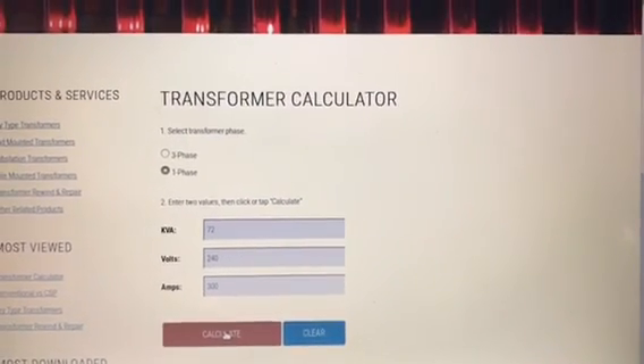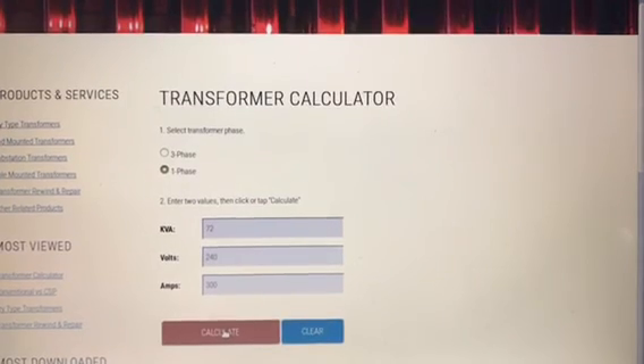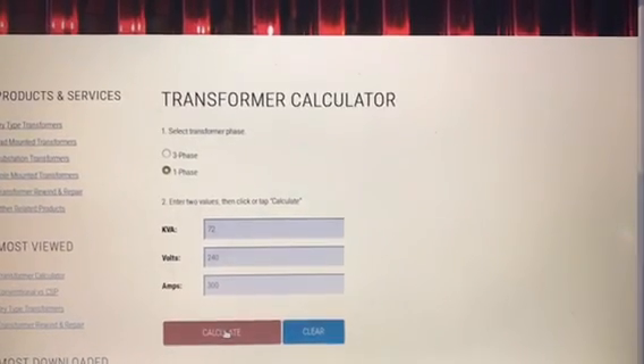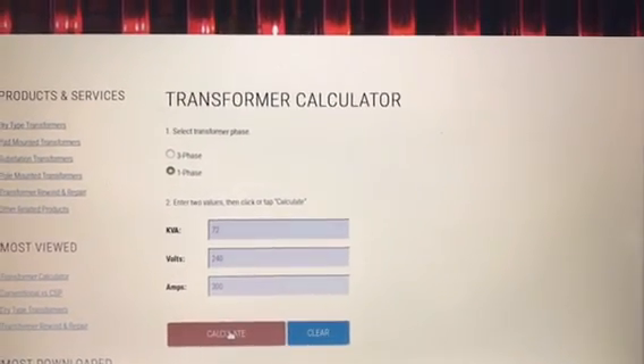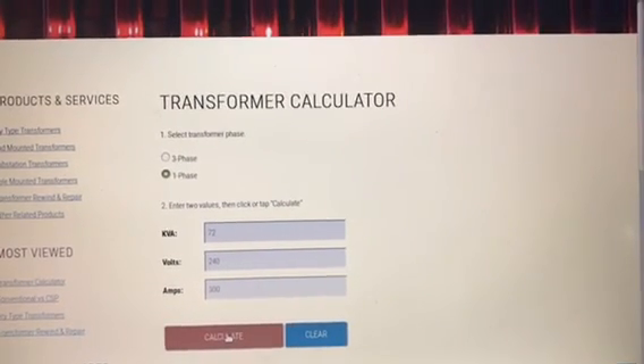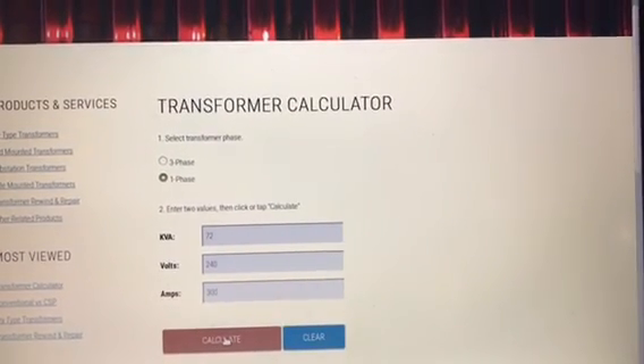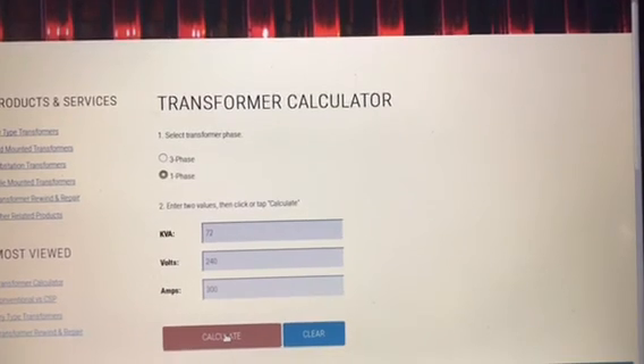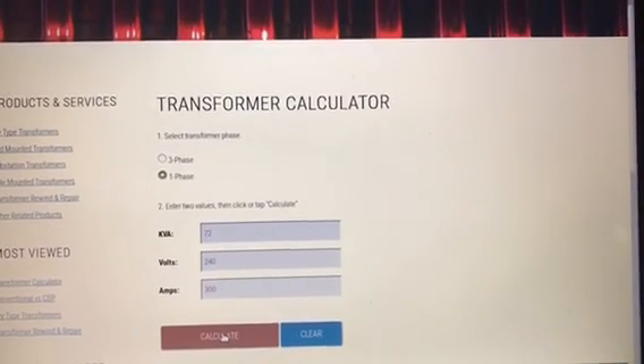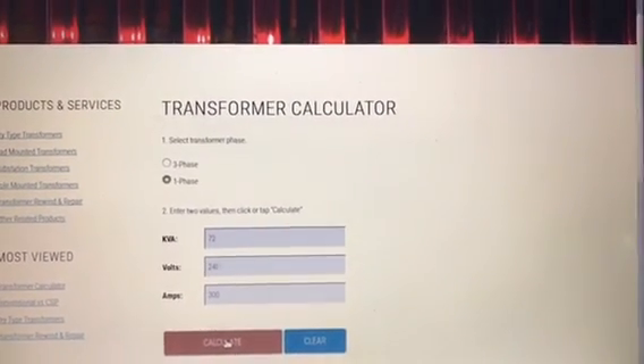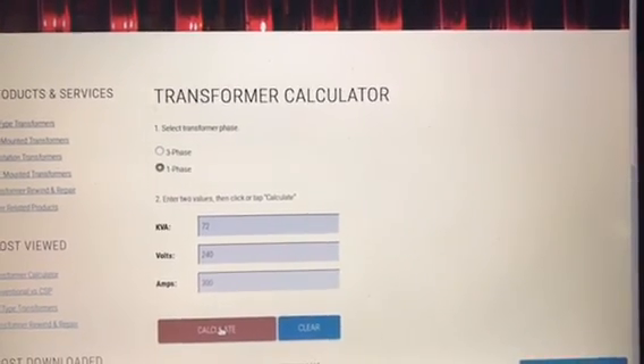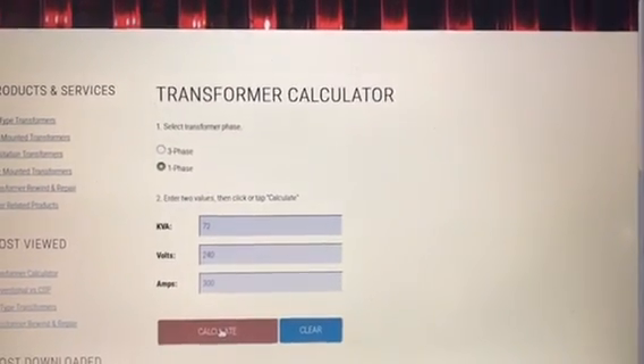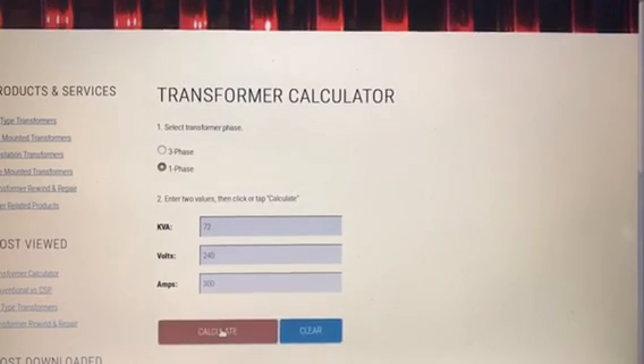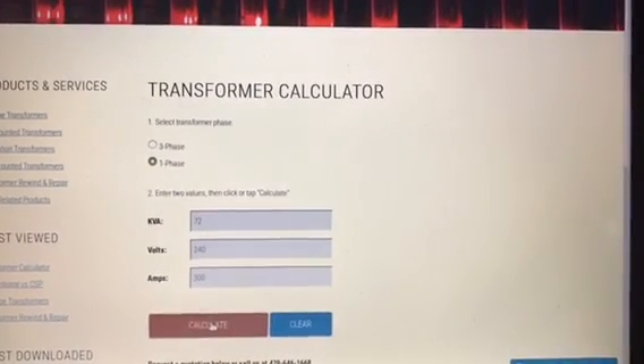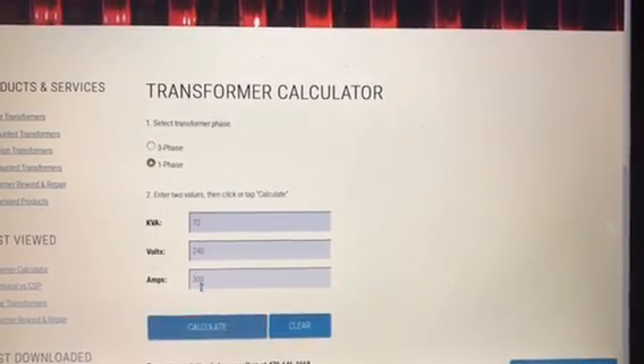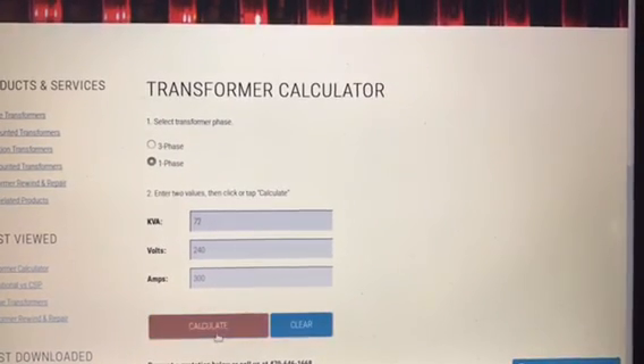Now when you're sizing a transformer, at least the power companies, they actually allow for some amount of overrating. So if I was in this predicament, I would probably allow a 25%, maybe at most a 50% overrating, say for an hour or 2 hours. But you should never run anything at 200% overrated for that long.